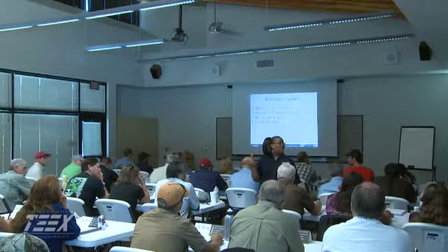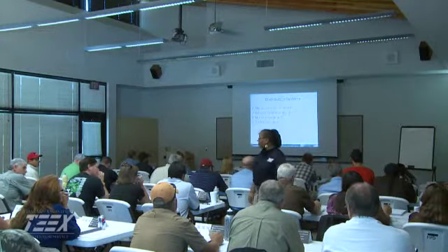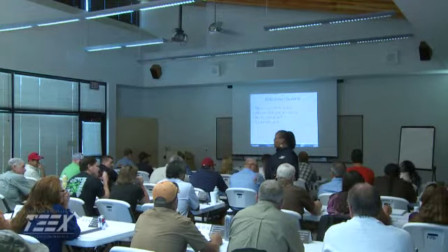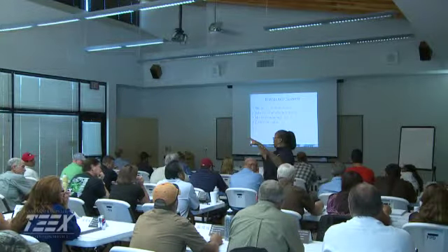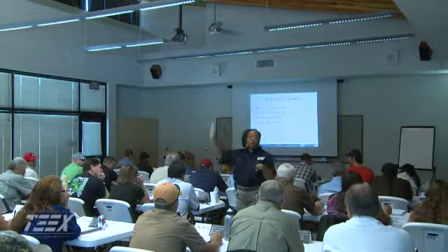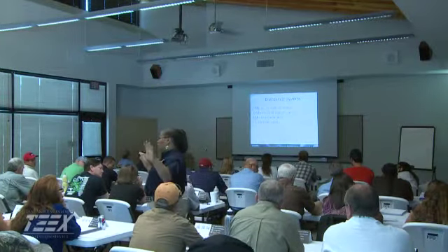What's another critical safeguard? Oh, he said cross connection control. Now that's another word for me. What's a cross connection? Okay, I had positive contamination, backflow prevention. So a cross connection is a physical connection between a potable water source and one that's treated to a lesser degree, one that may contain a contaminating substance, or one that I just don't know what's in it.